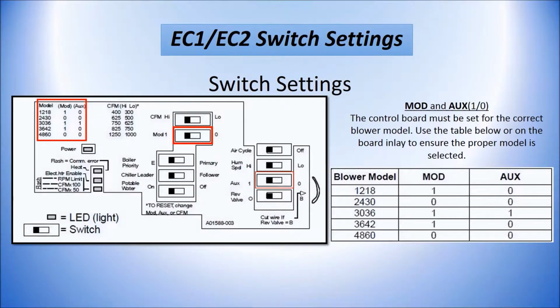The next setting is for the model. This involves two switches, the mod switch and the auxiliary switch. Each has two settings, 1 or 0. There's a table just to the left of the switches that tells you how to set the switches. The 1218, for example, is going to be mod on 1, auxiliary on 0. The 2430 is mod on 0, auxiliary on 0. From the factory, this is going to come set up as a 1218. If you do not set the model and you do not have a 1218, the motor will actually spin in the wrong direction and deliver no airflow.